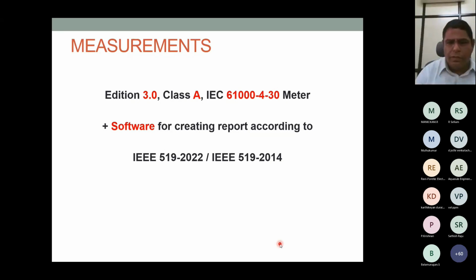So how a measurement should be done, I am telling you, it is edition 3. Edition 3 is the latest version which can measure consistently, and the accuracy levels will be there. Because it is revenue based, it has to go with an edition 3 meter, a class A meter complying with IEC 61000-4-30 standards. There are class A meters which are edition 2.0, which should not be used for measuring harmonics, because edition 3 and edition 2 have differences in the measurement methods.